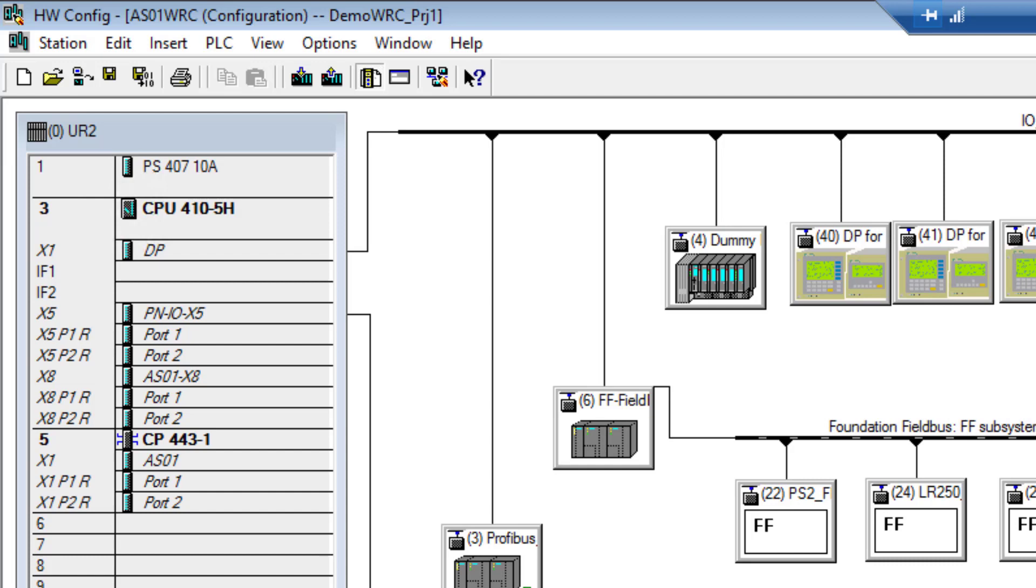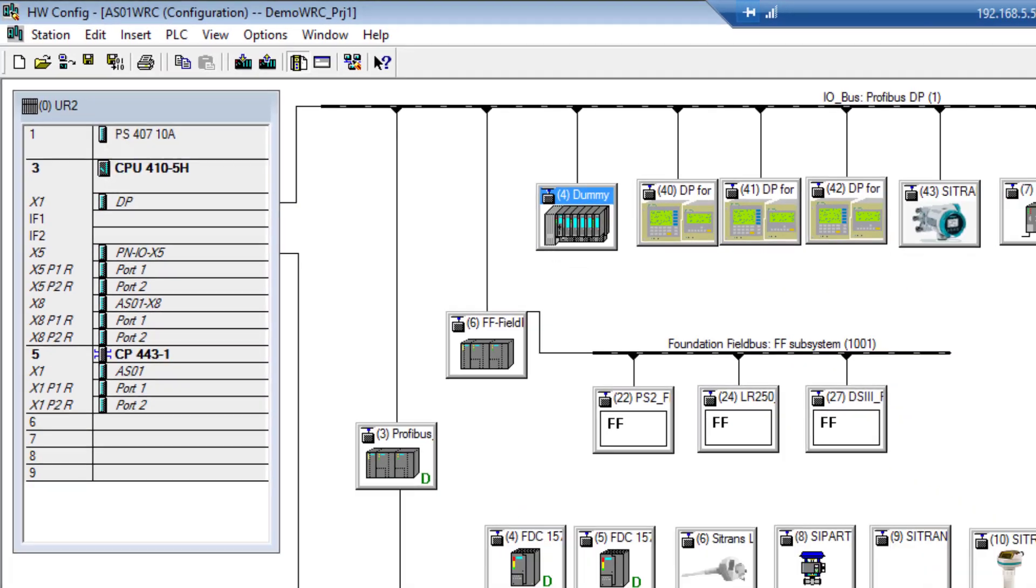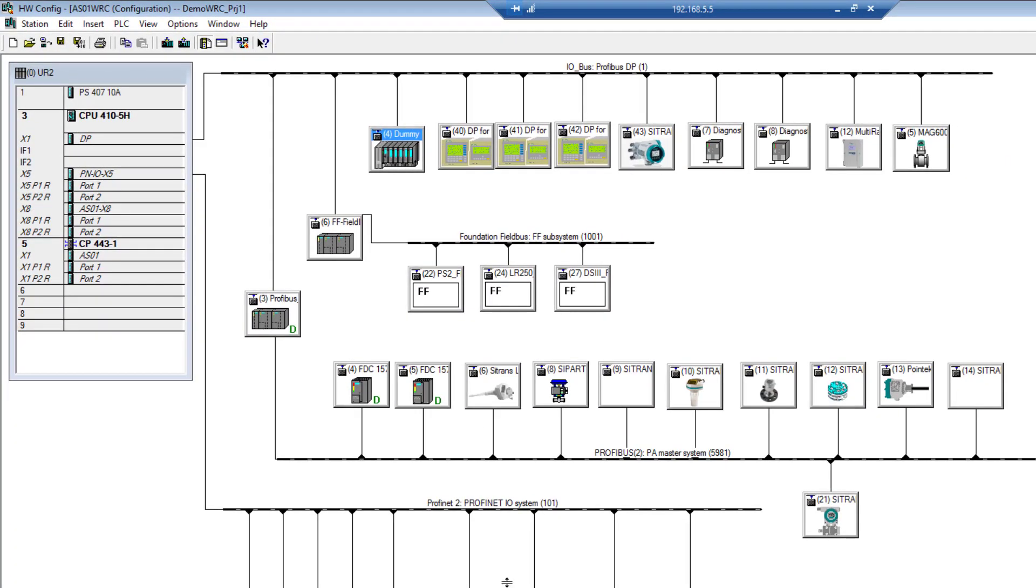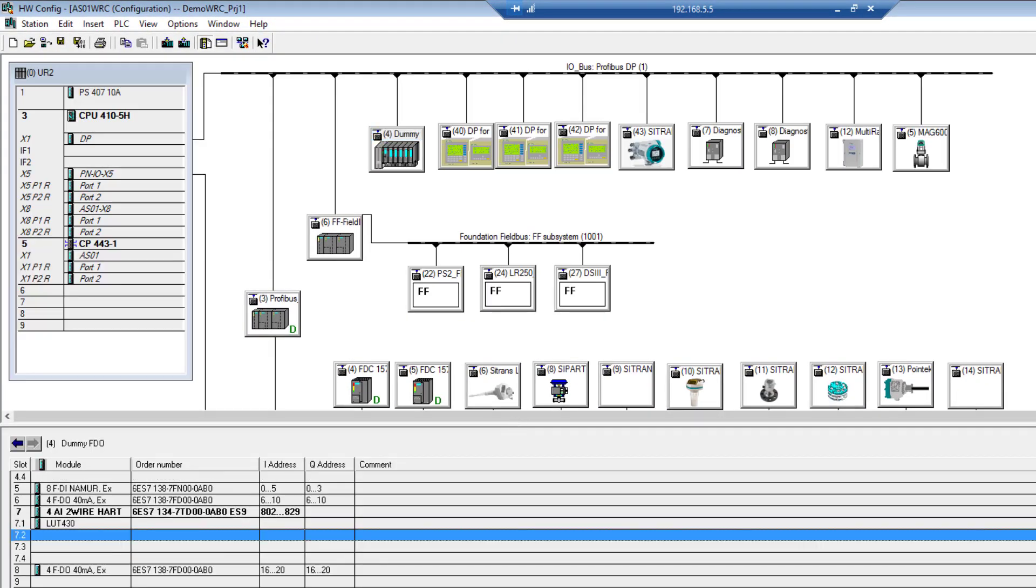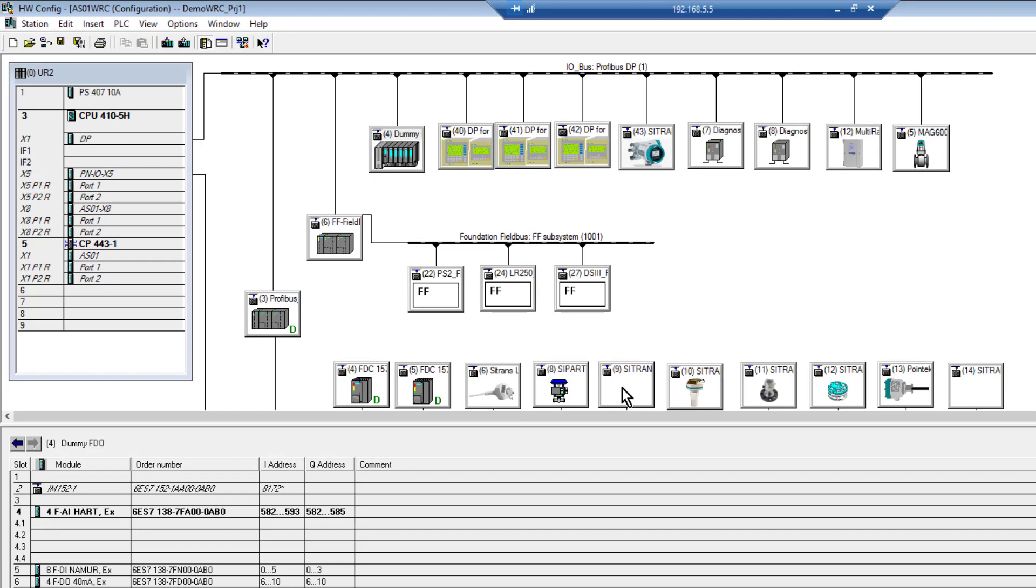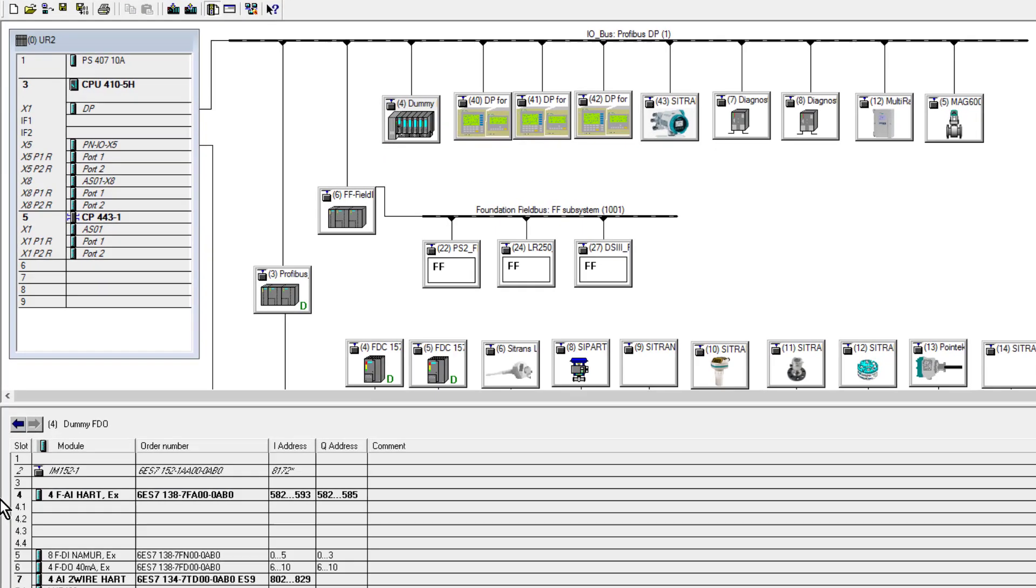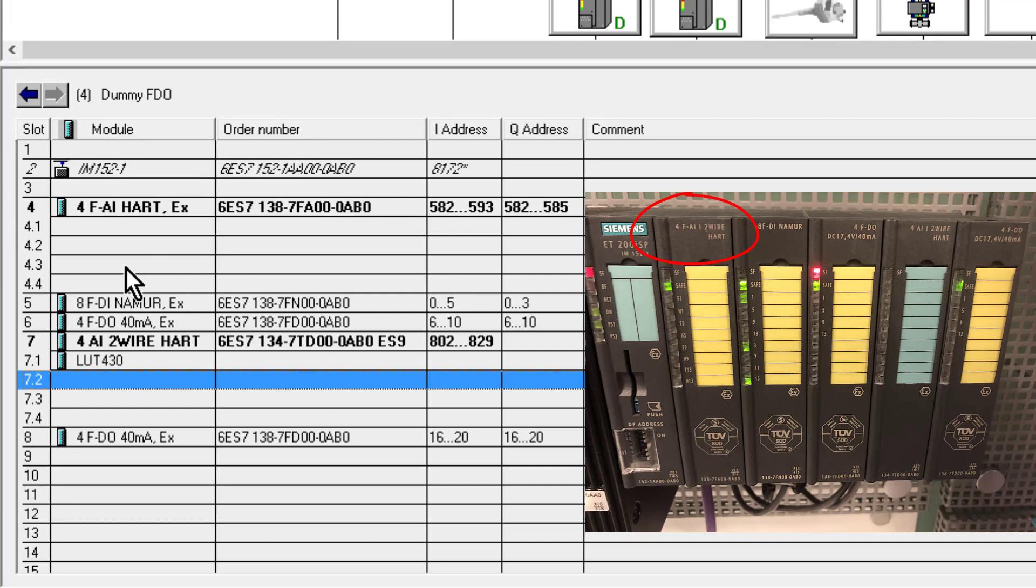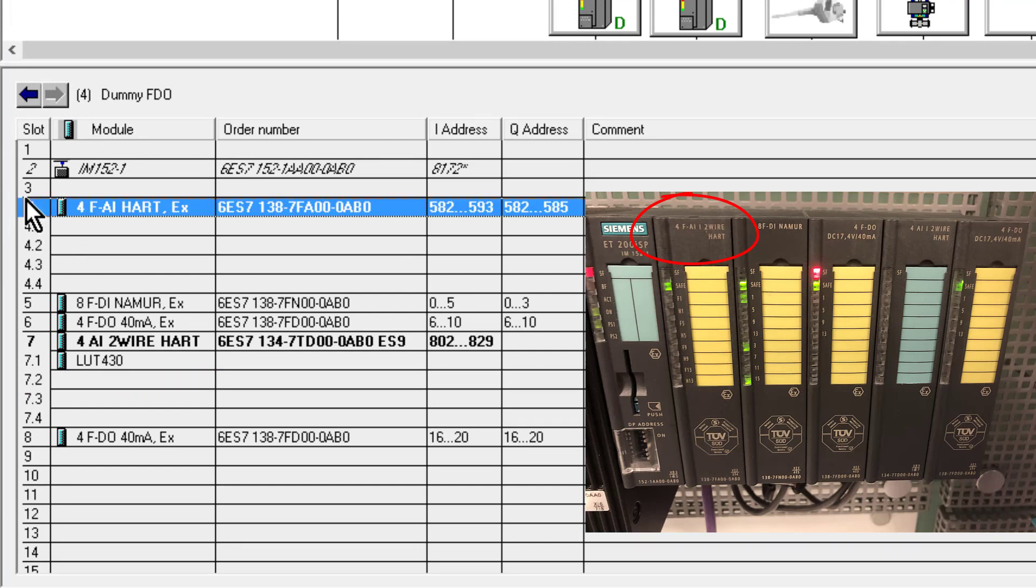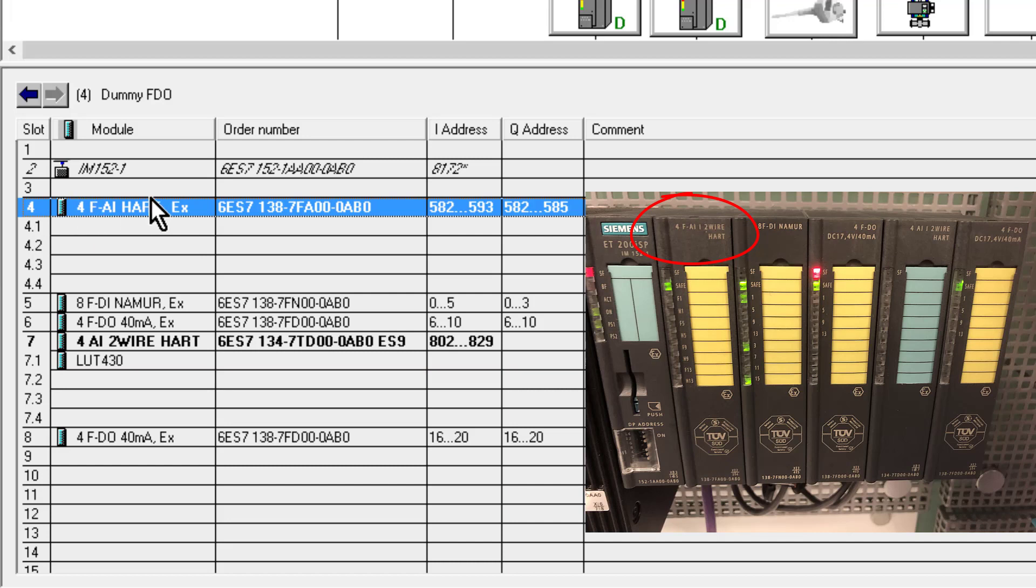The milliamp inputs, outputs, and digital inputs and outputs are all protected via barriers for zone 0 installation. Here's my ET200 ISP, and when you open this up you'll see all your different HART digital input cards. On my first slot I have an F, which is a safety module.